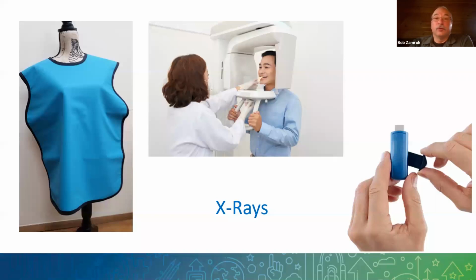But once a year, the machine should be calibrated, especially a 3D machine. Some manufacturers basically say you must do it, and I think all but a few manufacturers now have automatic counters on them for when they need to have some kind of calibration done, and they will keep giving you an error code that says calibration due, calibration due. You can always close out of that error code, but it's just reminding you that you need to have the calibration. So a lot of the 3D machines that we have, we are doing once a year. We're in there doing some kind of calibration or calibration check on that 3D machine.